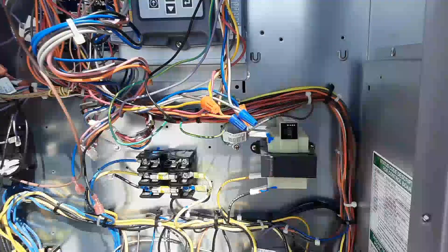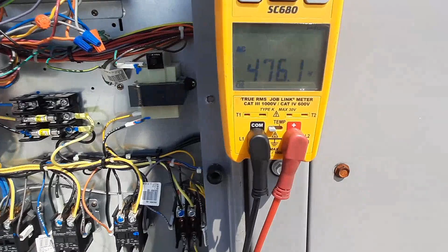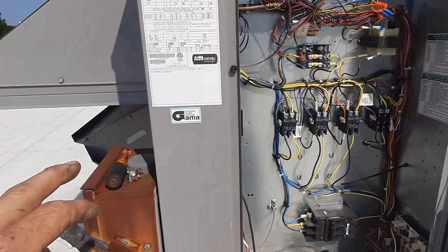So I was able to put it in test. I've got 24, 26 volts to my relay, and I'm getting 480 to my motor, well, to my plug at least. So I'm good from there to the plug. It's something on that side. All right, so I ohmed both of them out. This motor here on this side is still connected. I've got the other one disconnected, and we can actually go in here and test. So connect EX1, I know y'all can't see that. Run.